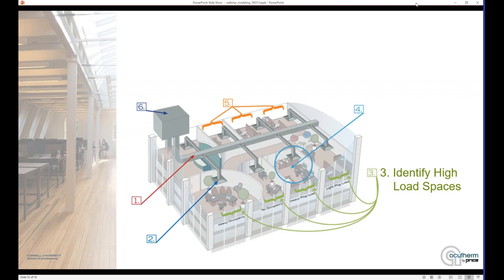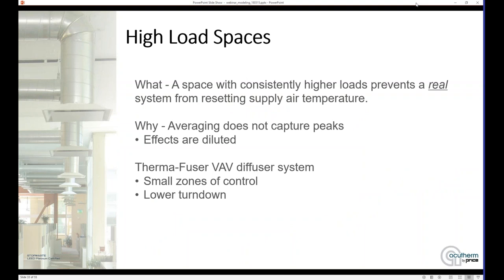Moving along, we're getting into more of a modeling approach now, and this is identifying high-load spaces. When you're in a real building, there are always spaces that have different loads from the ones nearby, and sometimes you have ones with consistently higher loads than their neighboring spaces. If you don't account for these in your model, the energy modeling software makes it easy to run averages across your building. That can be a quick way to set up a model but it's not a very accurate way — especially important with high-load spaces, because when you do have a high-load space, it causes peak loads in that one room that aren't in the other rooms.